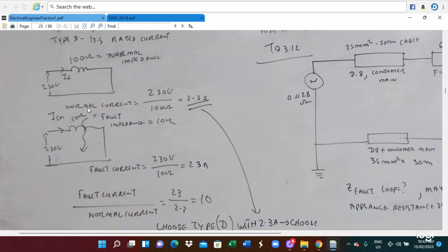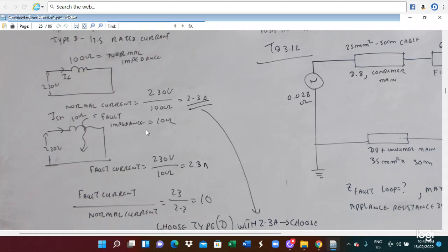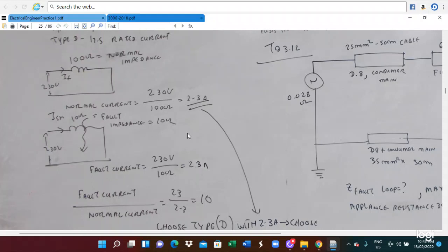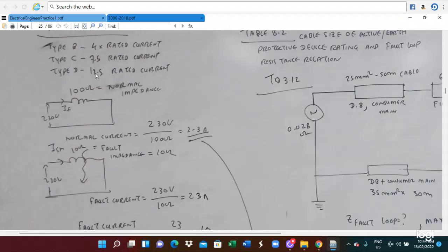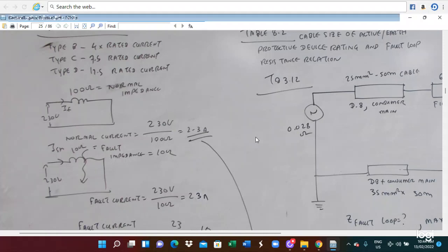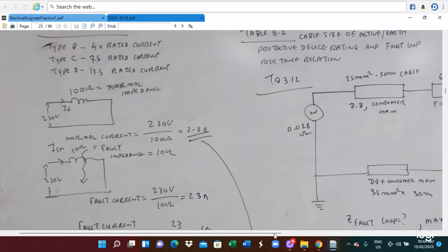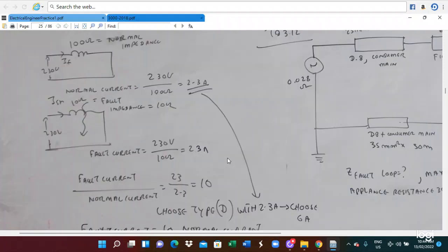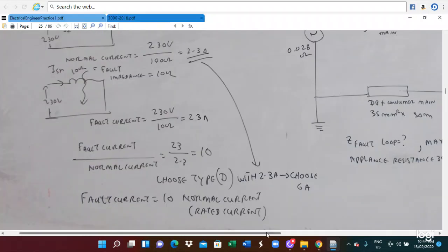You know the normal current, the normal impedance, and the fault impedance. Then you find the ratio between the normal and the fault current, and based on the ratio you select the type of the circuit breaker. Then, with the type of circuit breaker and the normal current rating, you refer to table 8.1 of the AS3000 2018 edition. Then you can find the appropriate fault loop impedance. So this is the way we calculate the fault loop impedance.